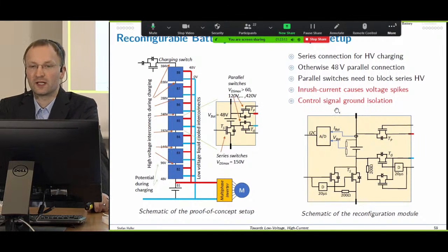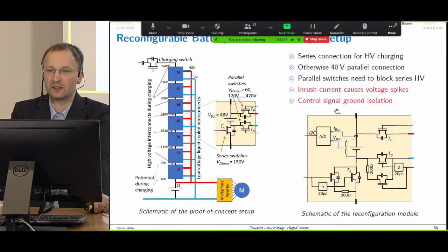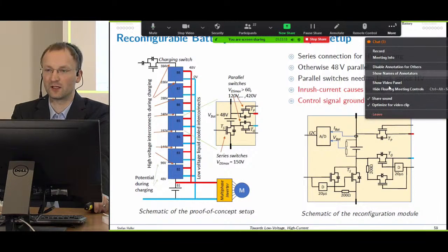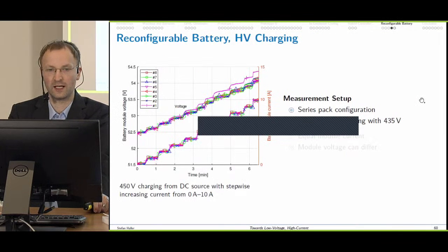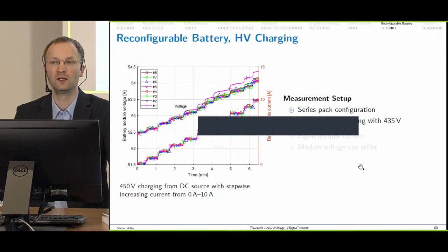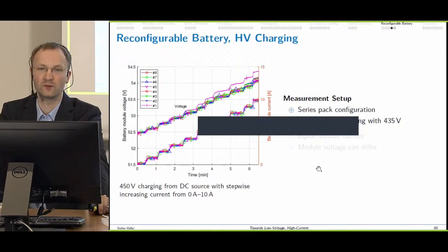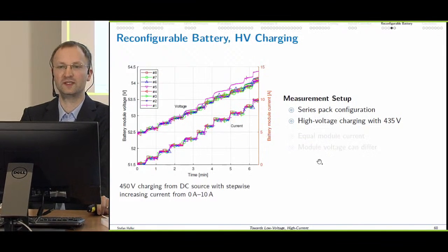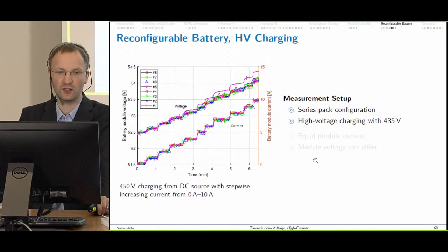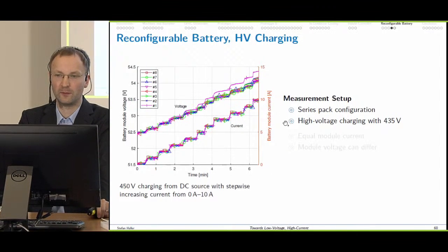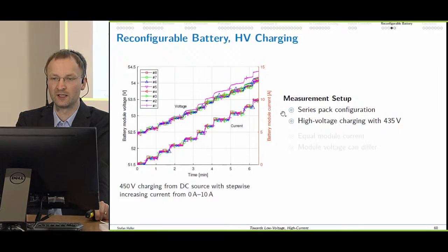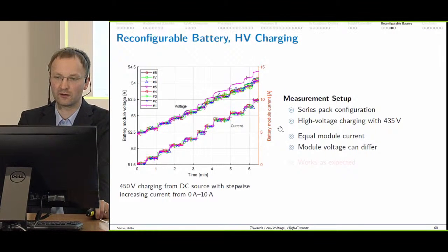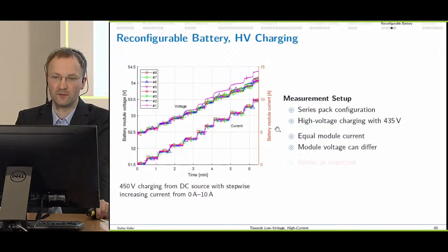And we also observed that it's a good idea to isolate the ground, so the control signals should have isolation. And that helps a lot to reduce the parasitic capacitance. So I'd like to show you 2 measurements of charging and discharging. What we see here is the high voltage charging with 450 volts. So the pack is in series configuration. That means we have equal module current and the module voltages may differ.